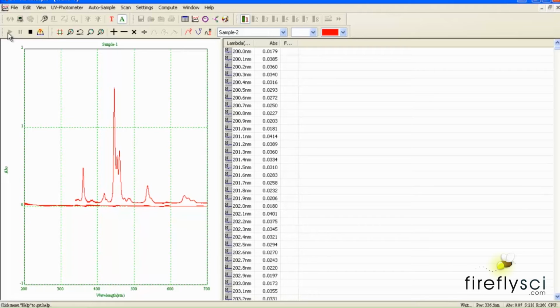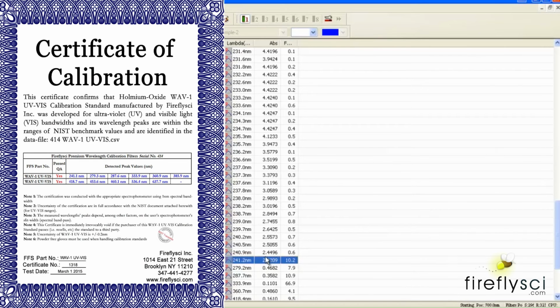When the scan is complete, we have to compare the peaks to the data on the Certificate of Calibration. So the first peak on our Certificate of Calibration is 241 nanometers. So our machine is showing a peak here at 241.2 nanometers, and their Certificate of Calibration shows 241.1 nanometers.